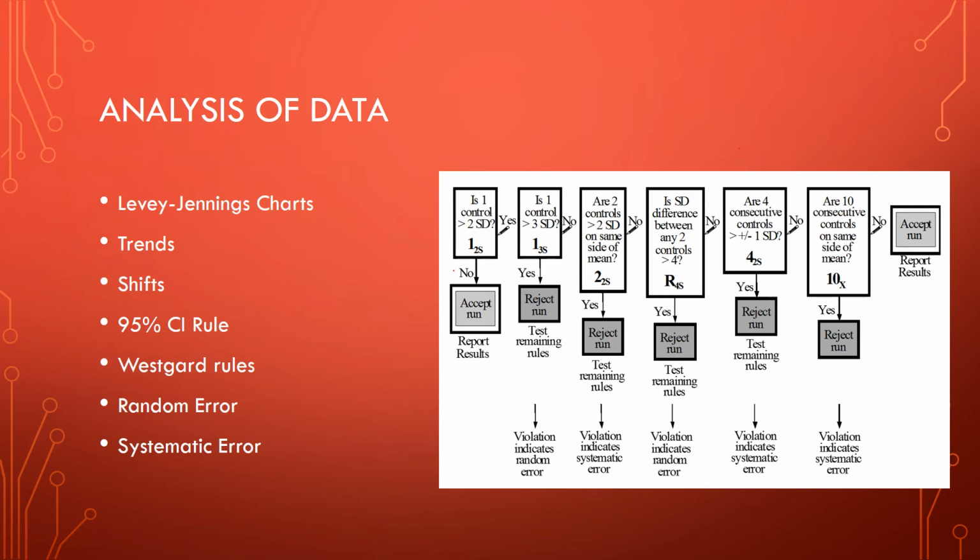You also can detect shifts. Shifts are when you have a complete change of the mean for the control material, with the new mean being continuous but different from the original mean. Usually, there's some flaw in the instrument in this case. A new mean should not come from deteriorated quality control, not when it's continuously new. So there's probably been some consistent flaw in the instrument or change.